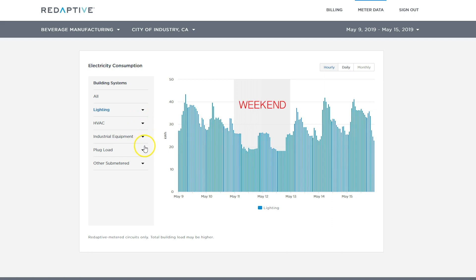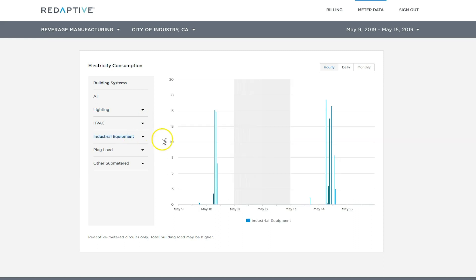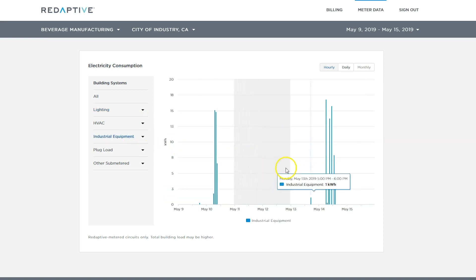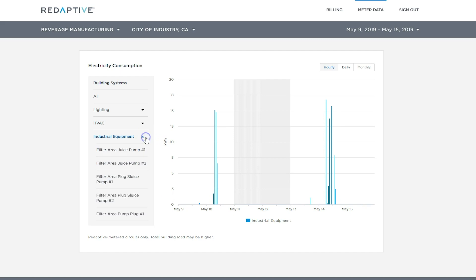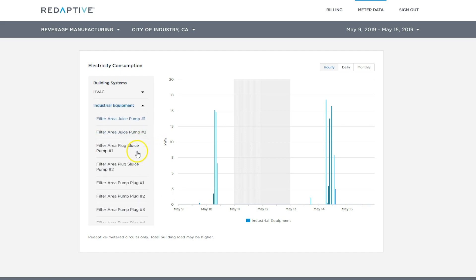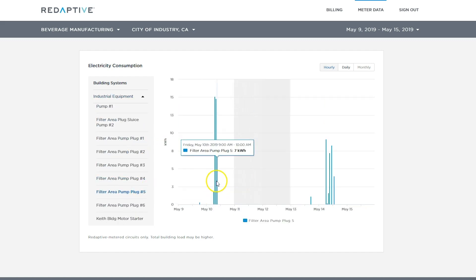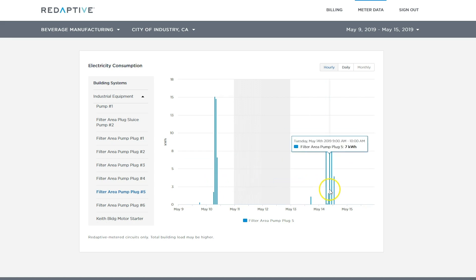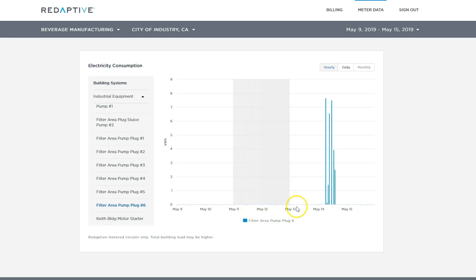This is where it gets a bit interesting. We can see some spikes in usage here that might be interesting to look into. We can drill into individual pieces of equipment and see what might be contributing to these spikes. Clicking through, we can see that the filter area pump plugs number five and number six are the main contributors to these usage spikes.